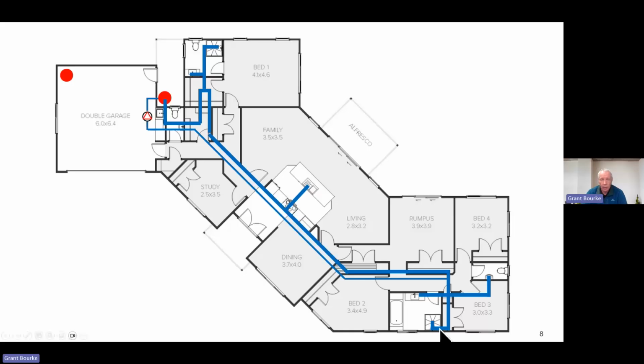So what we do is we add a small diameter pipe from the furthest fixture. We can now put the water heater plant anywhere we like, and we run a circulating pump which constantly pumps hot water around the ring main of the house and then back to the hot water plant. So now when I turn a fixture on at my kitchen sink, the water arrives near instantly, and other fixtures the same. Importantly, my distance called up under H1 for my pipe run is now very short because it's only the distance from the ring main to the fixture.